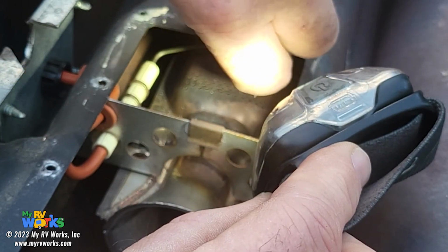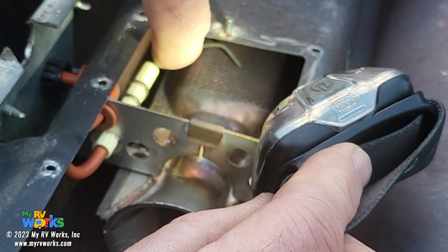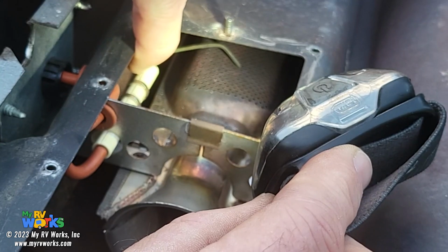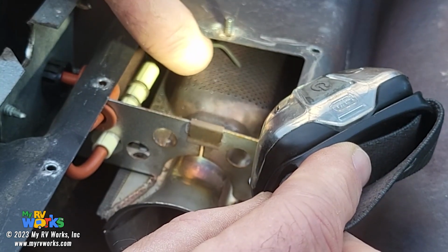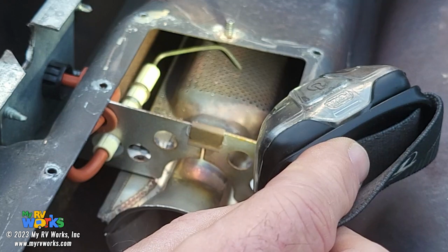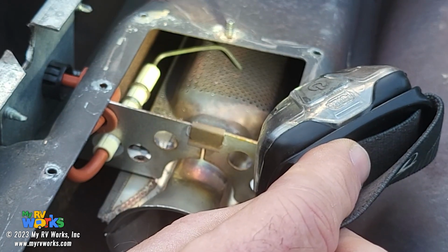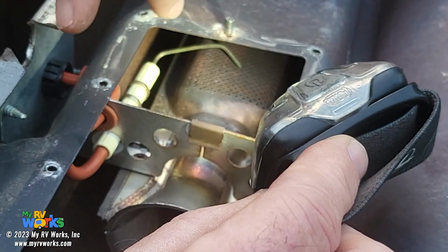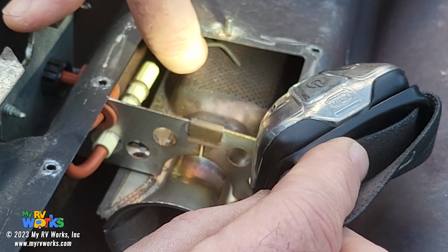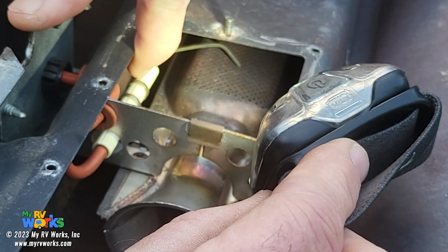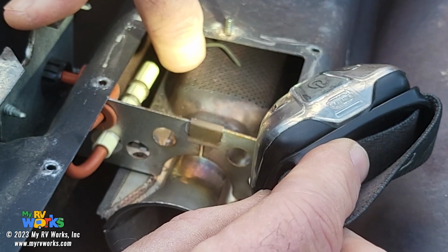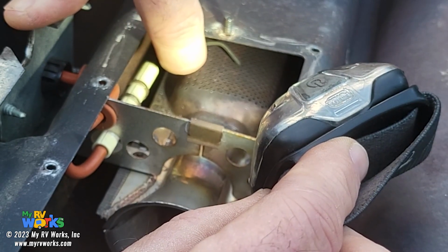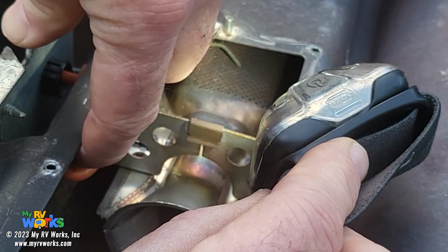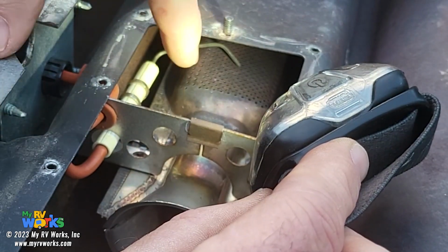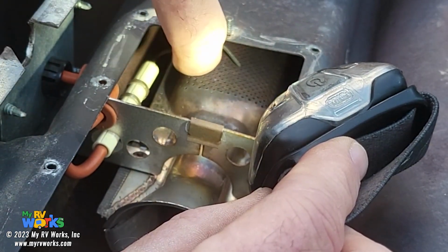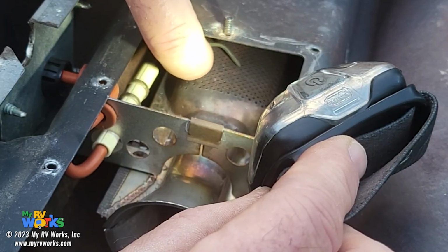So it's loose inside, this electrode is loose inside of the ceramic, is what I'm saying. Remember, I was saying that this intermittency will be because the control board cannot detect the flame. If this electrode wire, I'll call this the wire part, is loose within the ceramic, that will cause intermittent faults. Where they bond the orange spark plug gauge wire over to the metal inside the ceramic, sometimes those fault out, and that seems to be our issue right here.